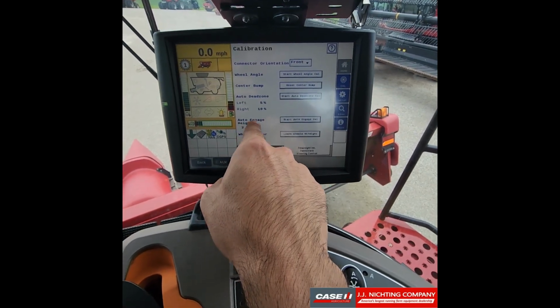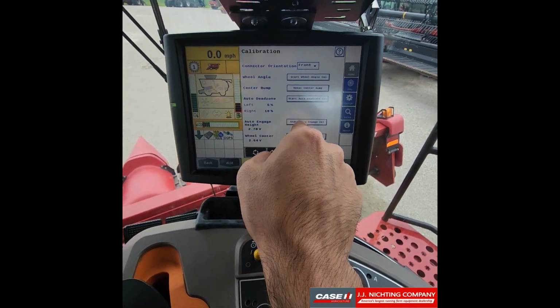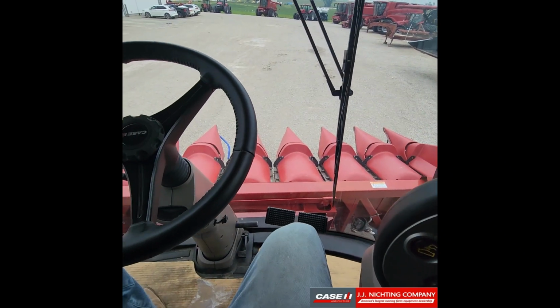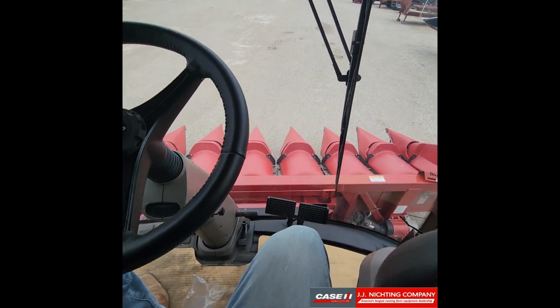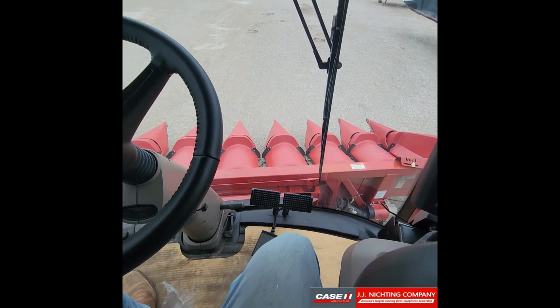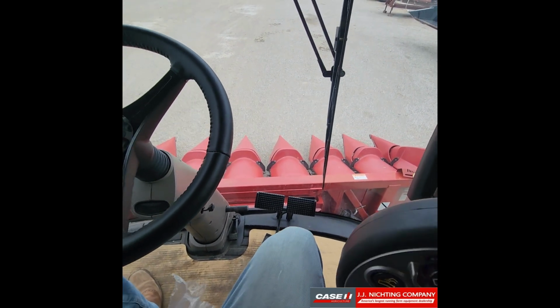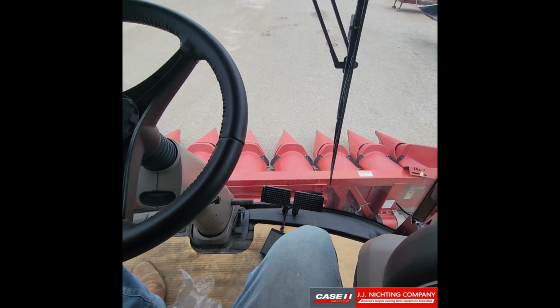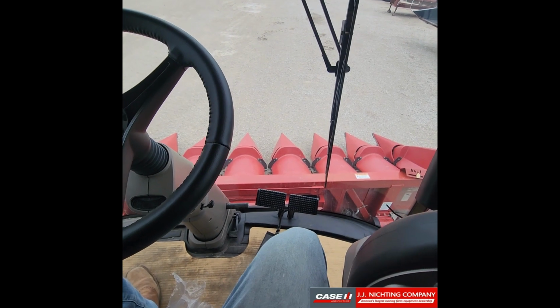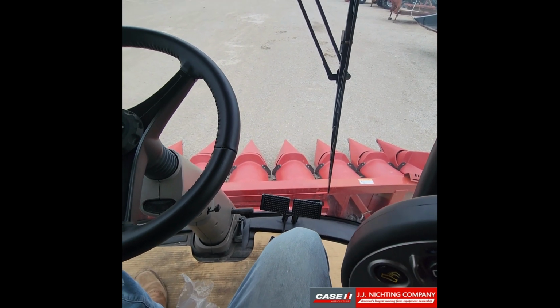Now we can do our auto engage height. To calibrate your auto engage height, what you want to do is lower the head to the height which you want the system to engage below. So once the system reaches that height, if you're going down, it will engage. If you come up above that height, the system will disengage.